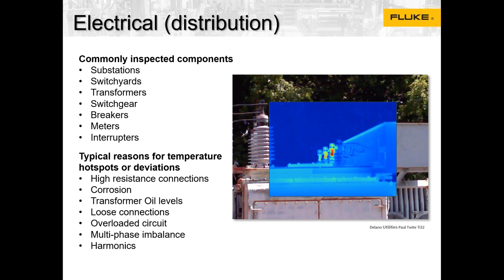So the typical reasons for a hotspot can be high resistance connection, corrosion, transformer oil level problem, loose connections, overloaded circuit, multi-phase imbalance, harmonics, a lot of problems. Also, it can be detected by a thermal camera, but you can also check with other products like power quality, or even vibration products or insulation testers.